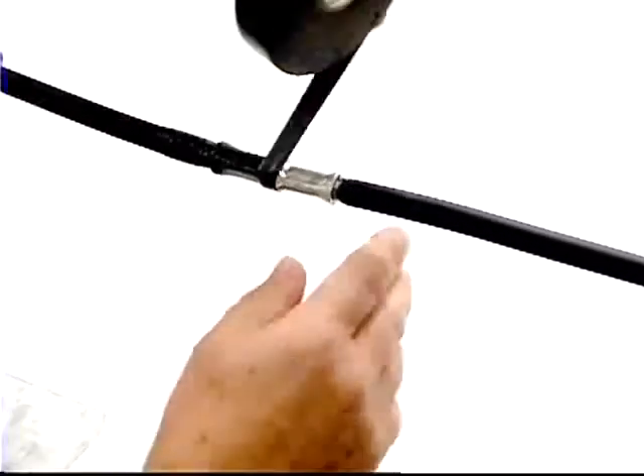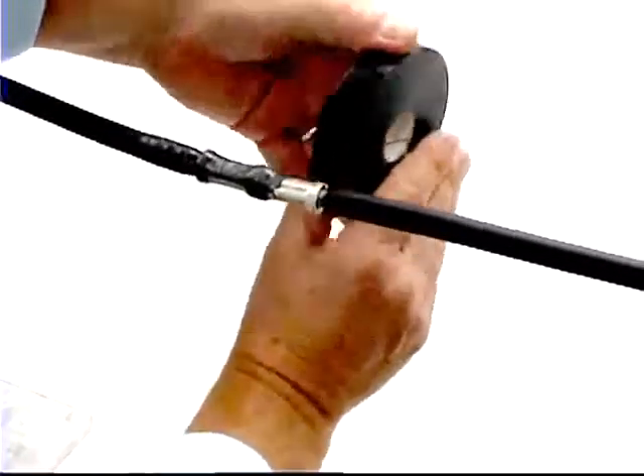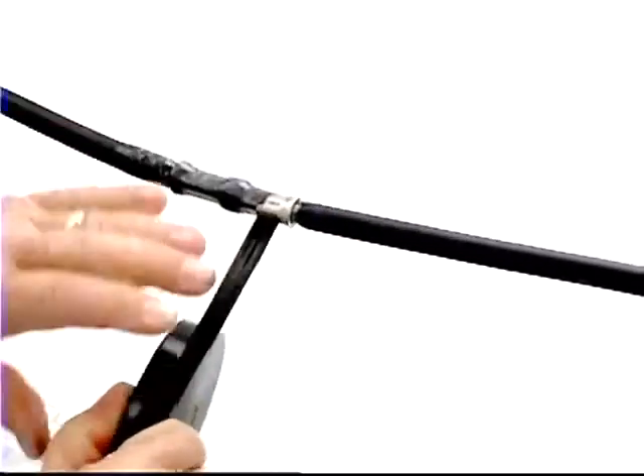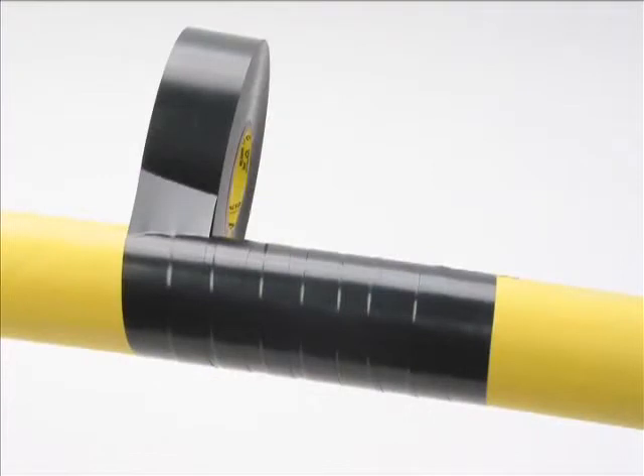Begin wrapping it around the connector with each lap of tape overlapping the previous layer by half the width of the tape. We call this method of wrapping half-lapping.